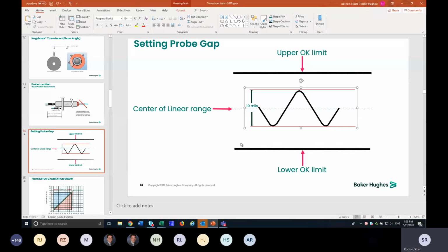Machines with quite large clearances, when you gap that probe, they're generally gapped or come in from the top. So your shaft is sitting down at the bottom, and you've got your lift oil, you have your oil wedge, all of those are going to lift that shaft up. So even if you gap it at a perfect negative 10 volts when the machine isn't running, it's not going to be a perfect negative 10 volts when the machine is running.